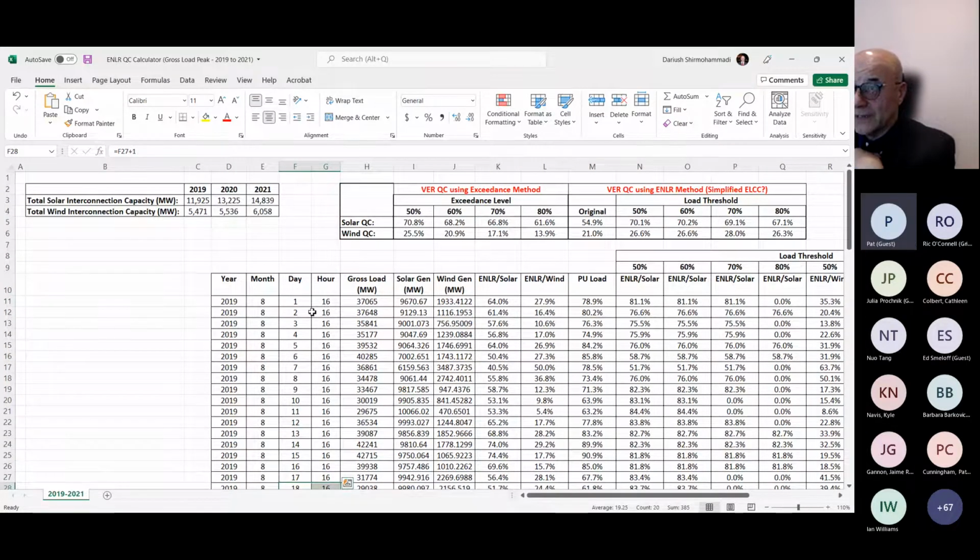We don't have all the data. We would have shown it and used it. The amount of solar and wind generation for the three years are here, and everything has to be adjusted accordingly. That's why everything is shown in percentages, because higher production in 2020 doesn't simply mean higher qualifying capacity, because we have more generation interconnected in the system. So we have to do all those adjustments in the calculation.